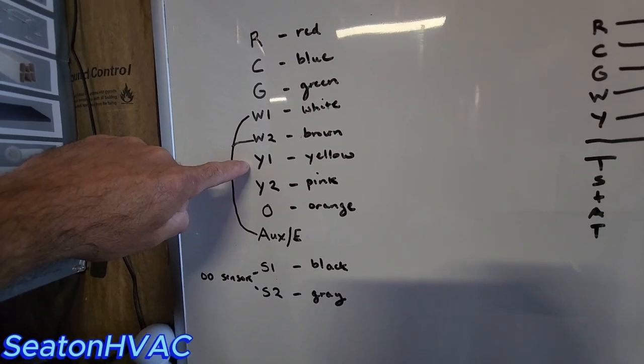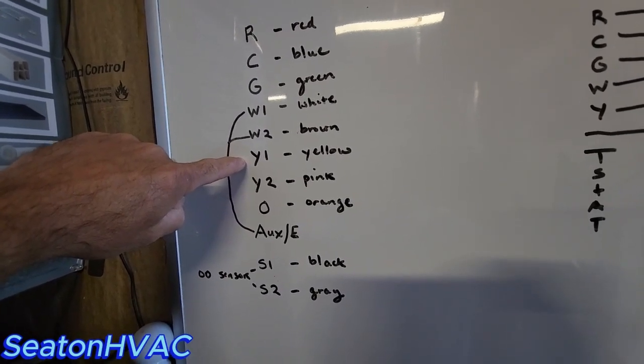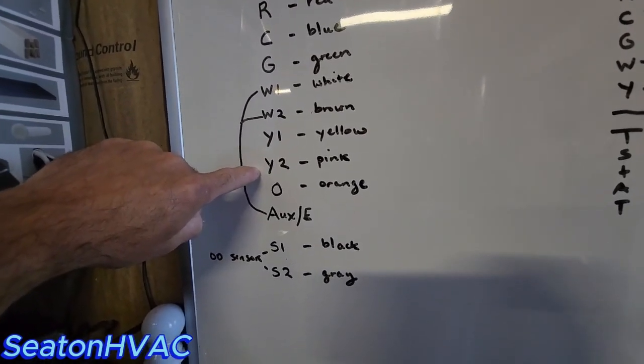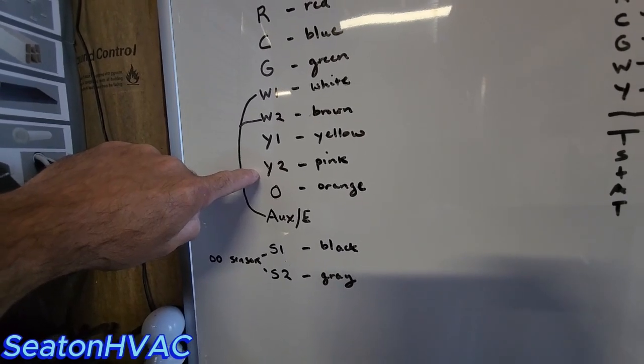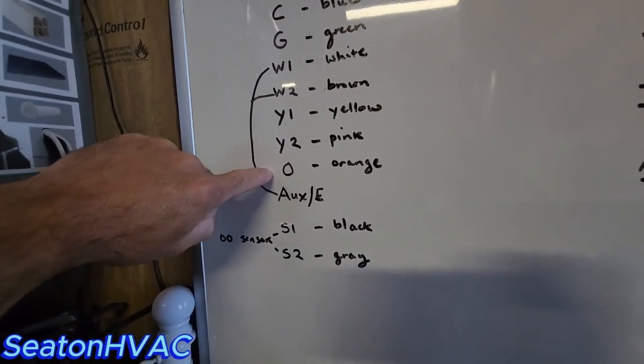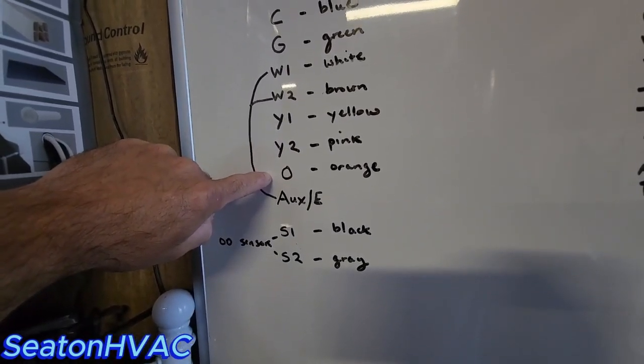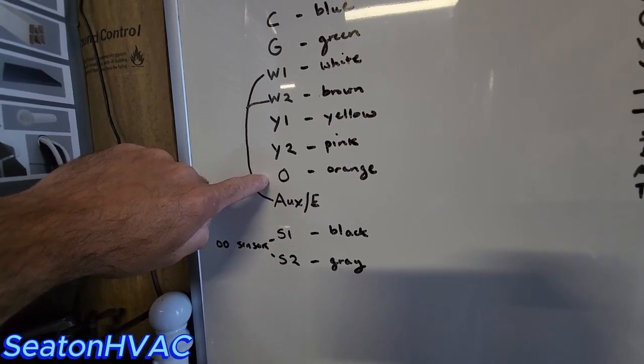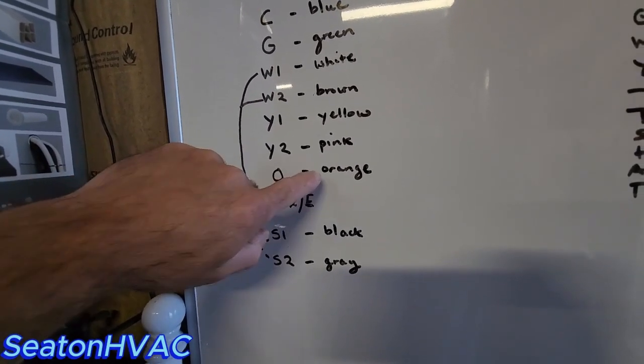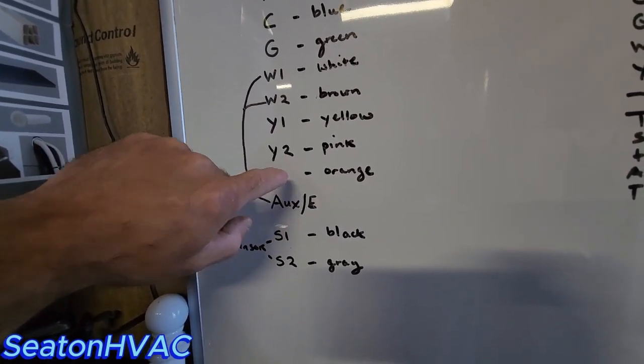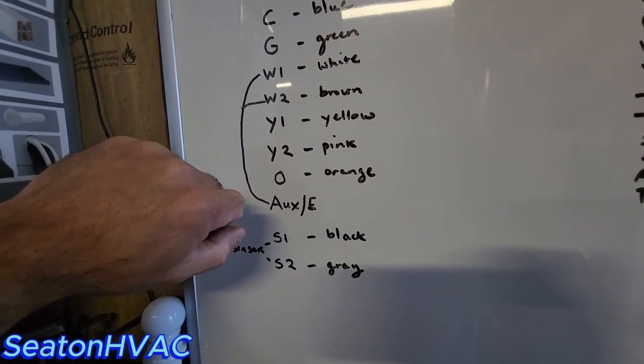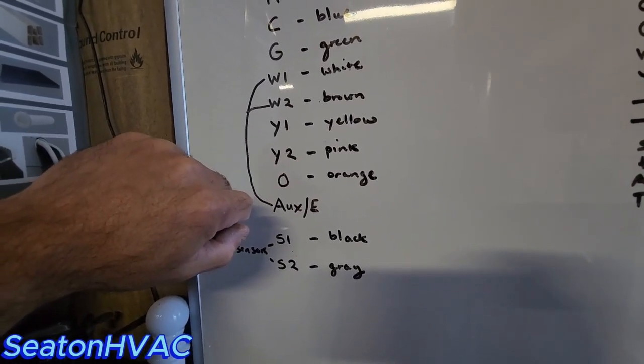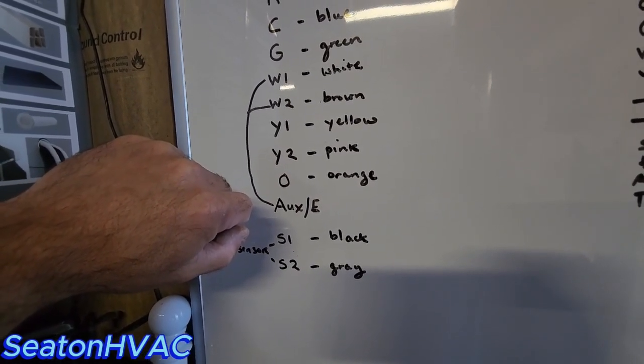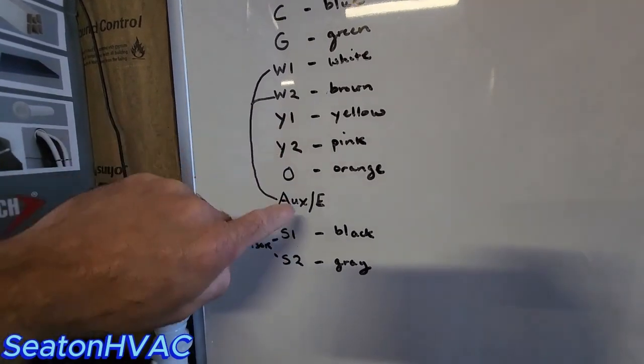Y1, your first stage of your compressor, your AC, yellow. Second stage compressor, Y2, I use pink. O for your reversing valve, I use orange. Now that can be O/B. I should put that there because some pieces of equipment use B for energizing the reversing valve. That means it's energized in heating side.